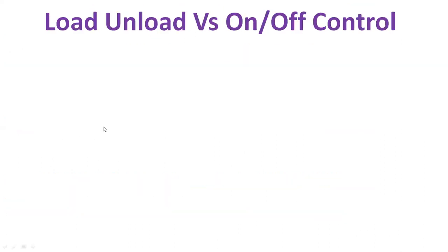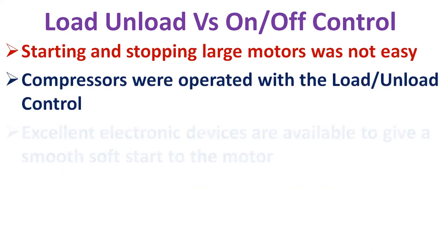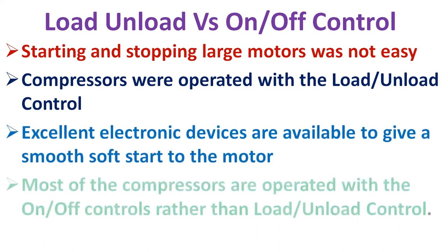In earlier days, starting and stopping large motors created stress on motors and starting devices, so compressors ran in load-unload mode — the motor kept running but the compressor did not compress air, meeting only no-load losses. Nowadays, excellent electronic soft-start devices give smooth motor starts, avoiding stress on motors and starting equipment. Their cost is much less than the savings from avoiding no-load losses, so most compressors are now operated with on-off controls rather than load/no-load control.